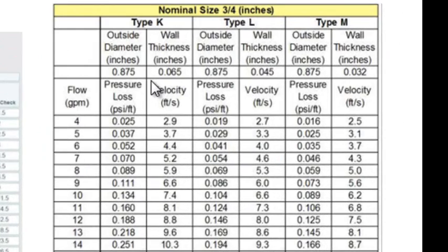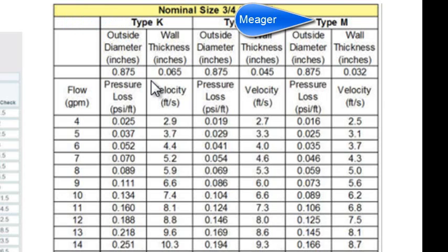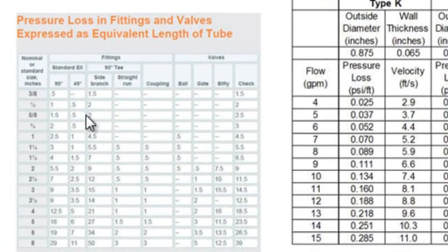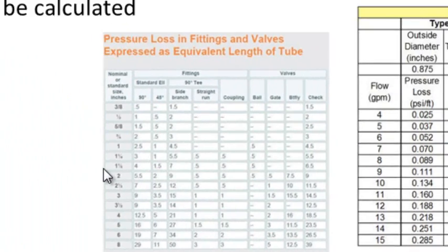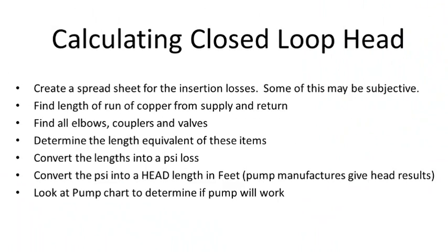How do we know what size of copper to run? Copper comes in different wall sizes: K, L, and M. K is king for the thickest and M is meager for the thinnest. L is usually the most typical wall size copper pipe we like to use, so we're going to go with L-type for our calculations. We're really trying to find a sweet spot, and sometimes we're going to have to make some subjective calls.